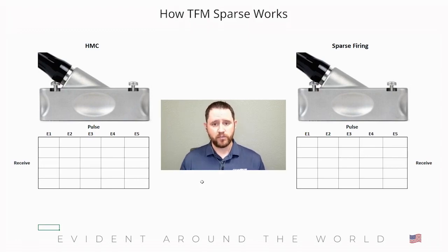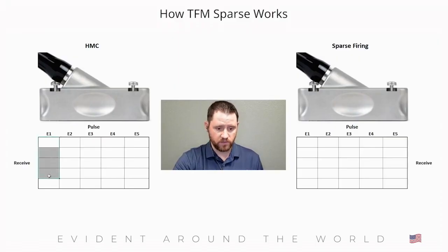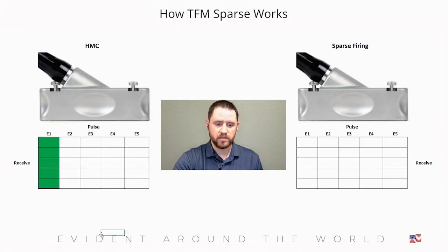So in a typical FMC process, we fire one element of the transducer and we receive with everything. In a half matrix capture mode, you begin by pulsing one element of the phased array probe and then receiving with all elements of that transducer. So on the left-hand side here, we have our half matrix capture setup with a transducer that has 5 elements in the transducer. And we'll go ahead and pulse number 1 and receive with elements 1, 2, 3, 4, 5, all from the phased array transducer. And let's highlight those green to simulate that we've received on those elements.